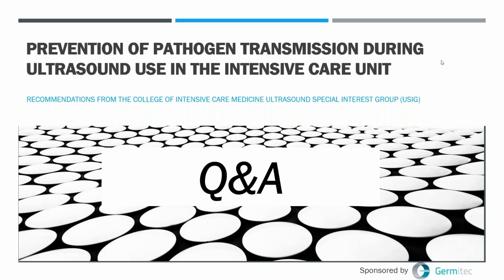Within the guidelines, we have recommended the push towards touchscreen only. I see it as the only viable long-term option within intensive care practice. But it is a dilemma. You certainly are free to use hospital grade, but will that be more damaging to the machine? The other thing to consider is the residual product that you're going to be touching. Certainly with high-level disinfectants, depending on how they are used, there is a little bit more nuance than the binary decision than what I've said. One does have to choose between high-level and low-level.